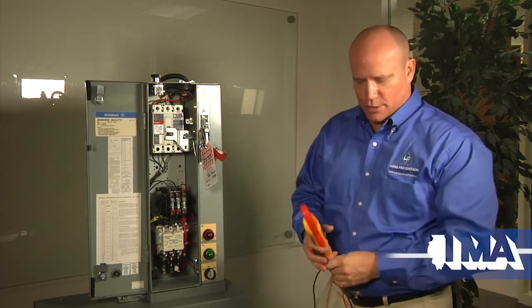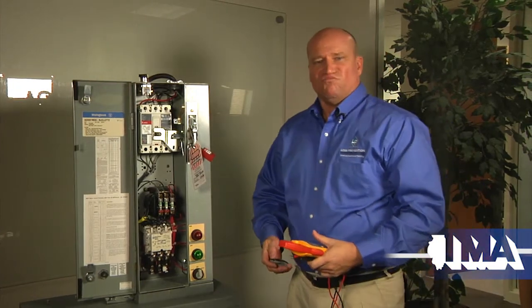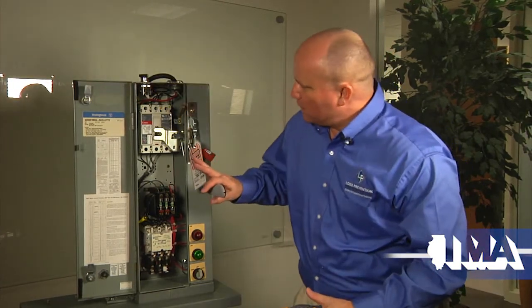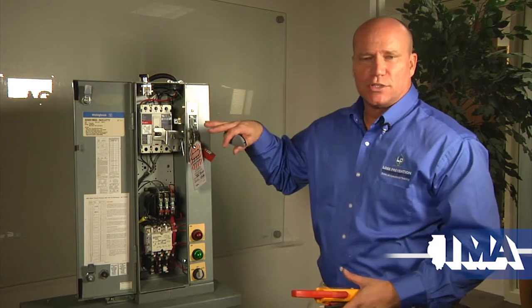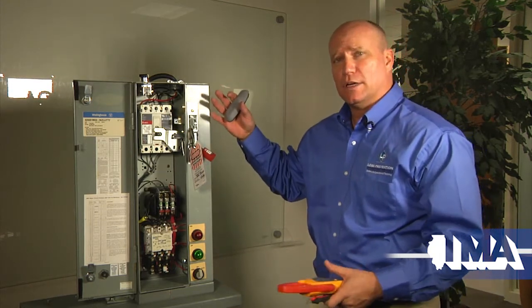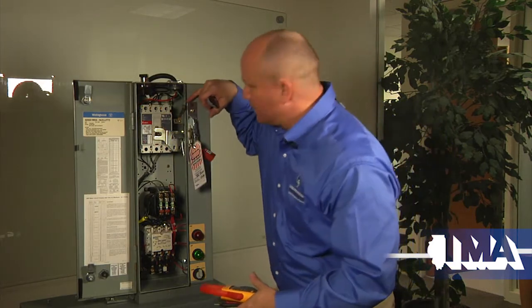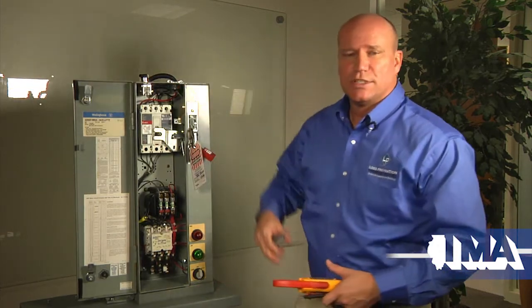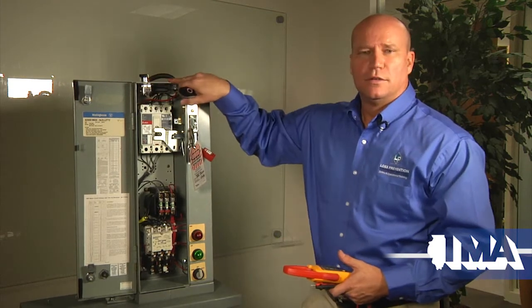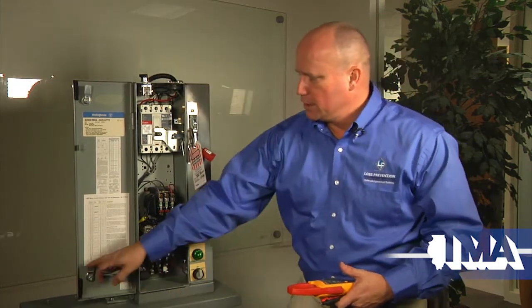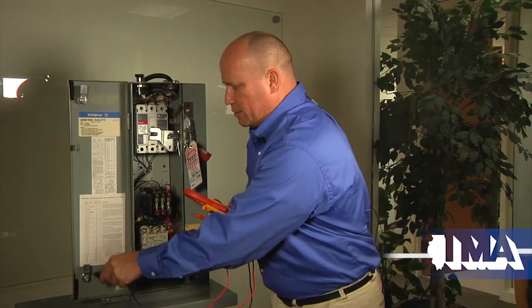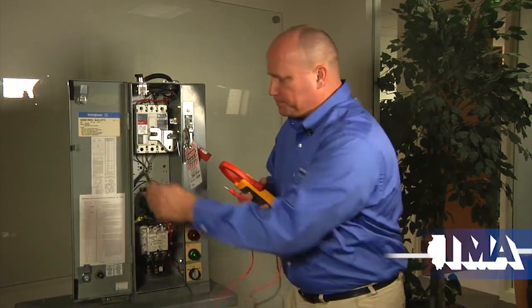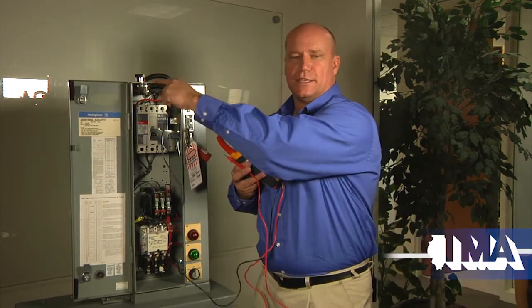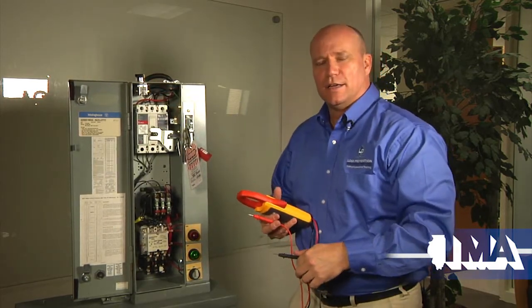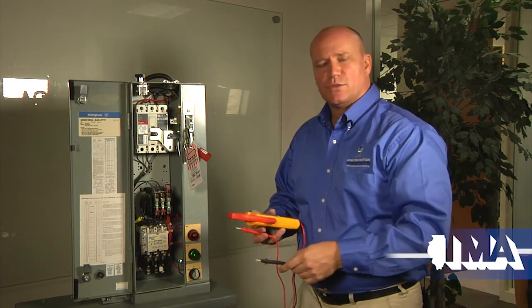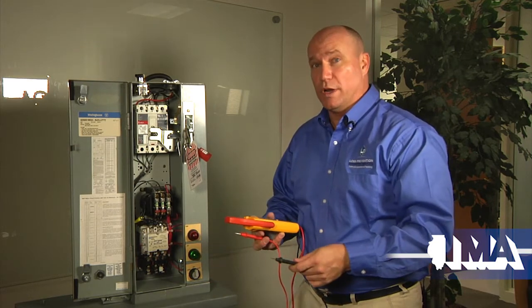Okay, the next thing, as I progress through the slides, is you've got to find an appropriate ground point. Anytime you're in an enclosure like this, you're going to have a green or a green and yellow lead, with a contact or a point right there, which is a good ground point. Don't use metal, which is normally painted metal. Don't use the door, I've seen that, because this is not good continuity from the hinges on. And paint and also rust, even if there's no paint in place, can reduce continuity. You want to have the lowest resistance path, a good zero reference point, when you're doing these tests.